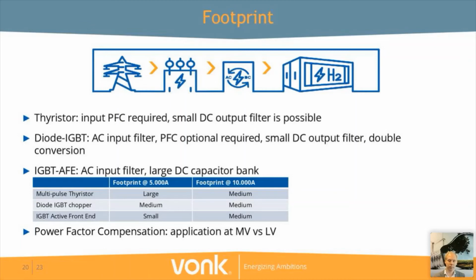However, looking at it at a larger level of current, for instance at 10,000 amps, what you see then is with an IGBT active front end, you would need significantly more IGBT stacks, causing the relative footprint to go up, and a multi-pulse thyristor solution probably mostly only needs larger thyristor stacks. So at that kind of current level, the relative footprint sort of evens out. In any case, the effect of the diode IGBT chopper with regards to additional equipment, as well as requiring more IGBT stacks, is somewhat in the middle.